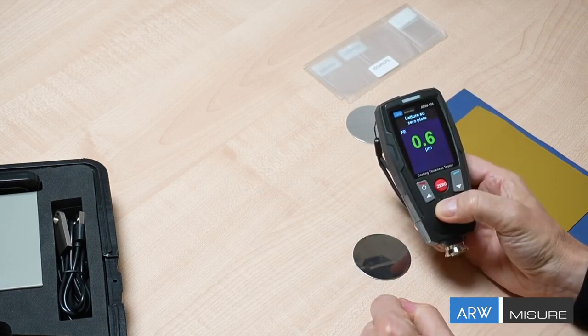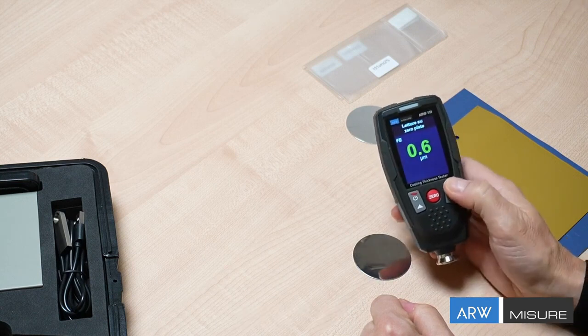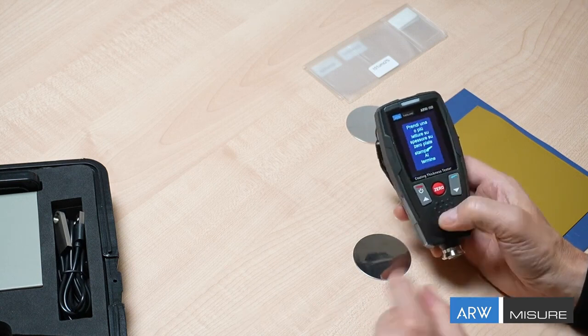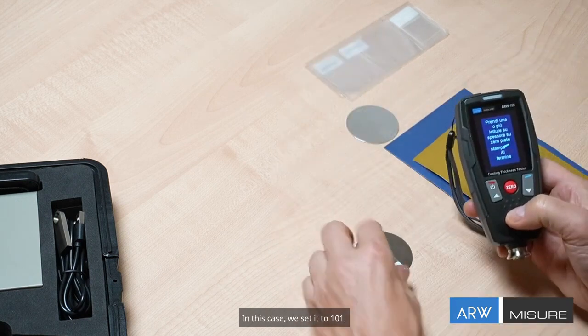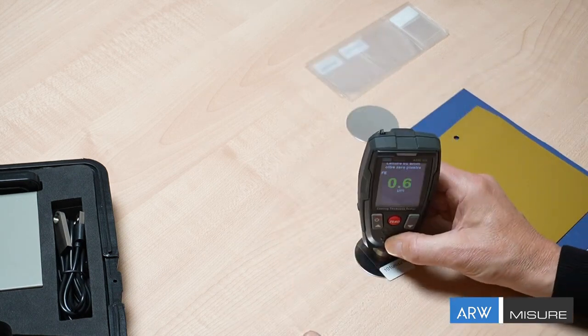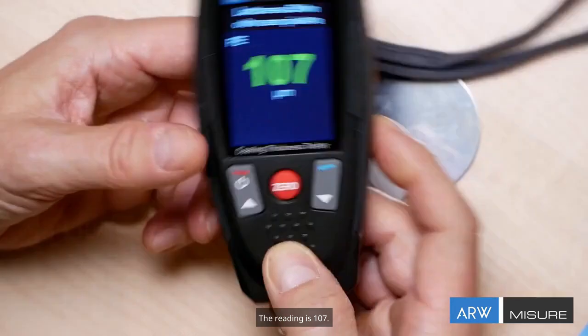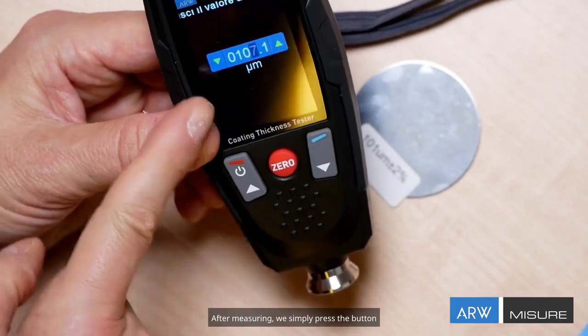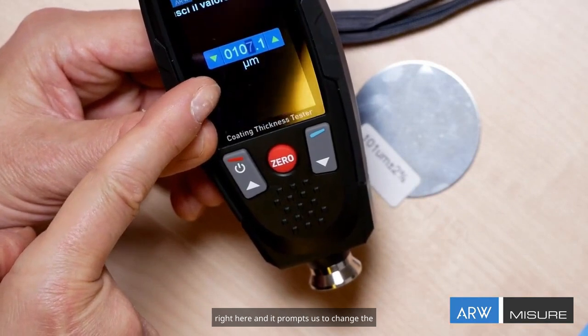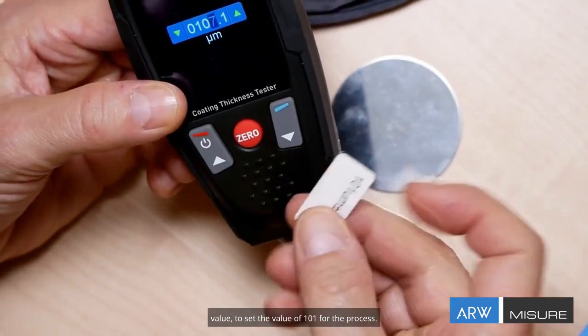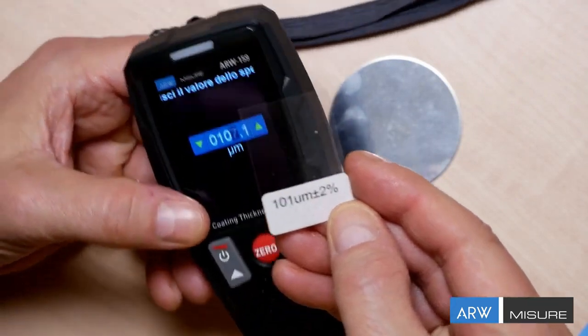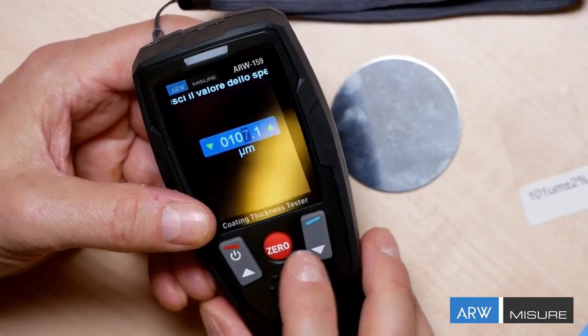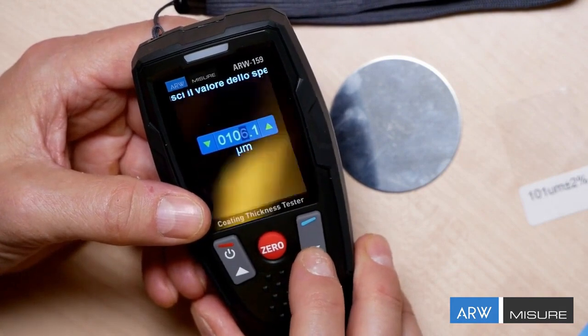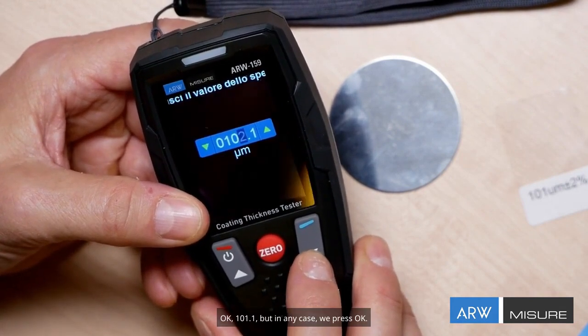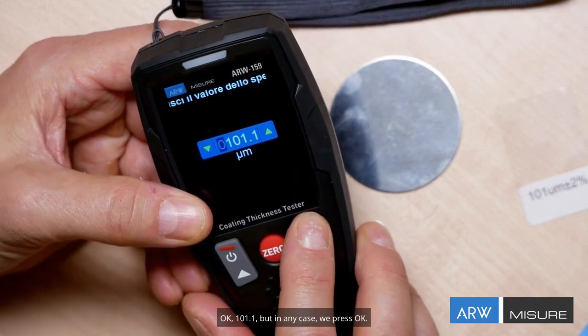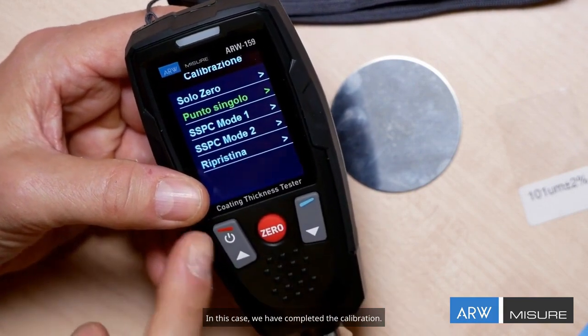Okay. We confirm by pressing OK. It asks us to place a thickness gauge. In this case, we set it to 101. The reading is 107. After measuring, we simply press the button right here, and it prompts us to change the value, to set the value of 101 for the process sample. We use the arrow keys. Okay, 101.1, but in any case, we press OK. In this case, we have completed the calibration.